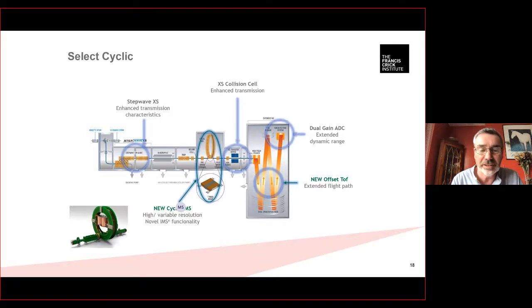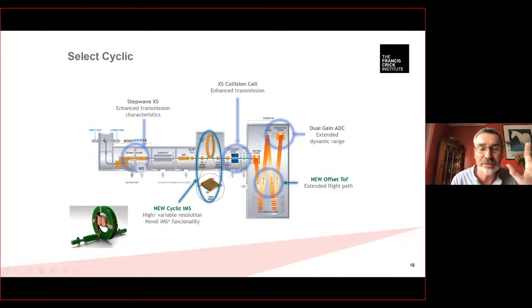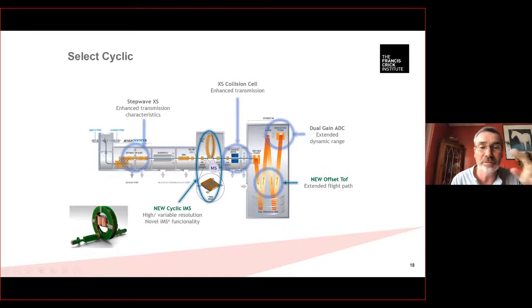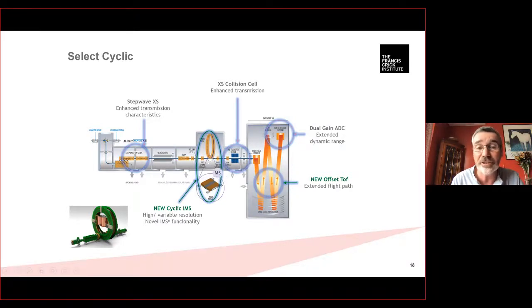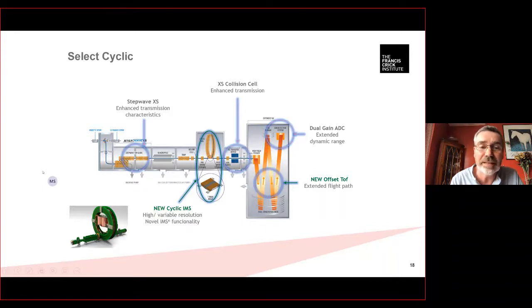The cyclic instrument features a circular T-wave ion mobility cell where ions can make multiple passes, effectively increasing the separation path length. Resolution in mobility is increased and it has a new time-of-flight analyzer with resolution up to 60K in V-mode and 100K in W-mode. An array diverts ions into the TOF or can select a particular species as they come around the ring. This instrument potentially offers major advantages for looking at highly complex structures, and we also seem to get reduced back exchange with the step wave at the beginning.